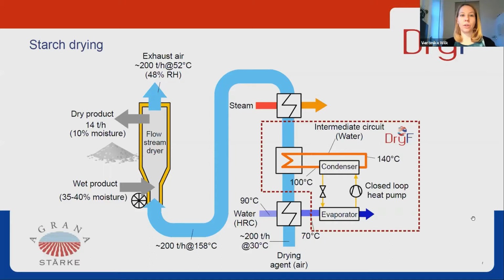On the right side we have the installations needed to heat up the drying air. The first heat exchanger uses water from a hot water cycle, the heat recovery system they already have in place, collecting waste heat from other installations. This water cycle has a temperature of 90 degrees C and is used for preheating; after the preheating step the water cycle still has a temperature of 70, and the air is heated to approximately 88 degrees C.